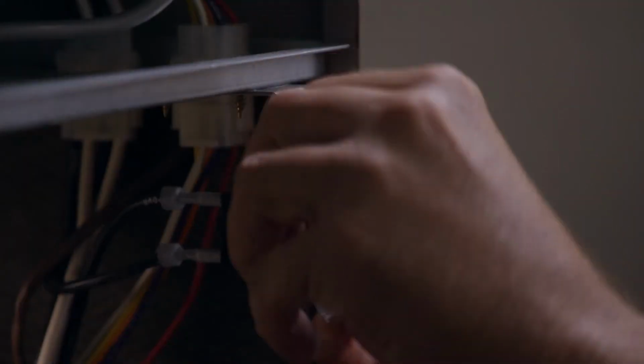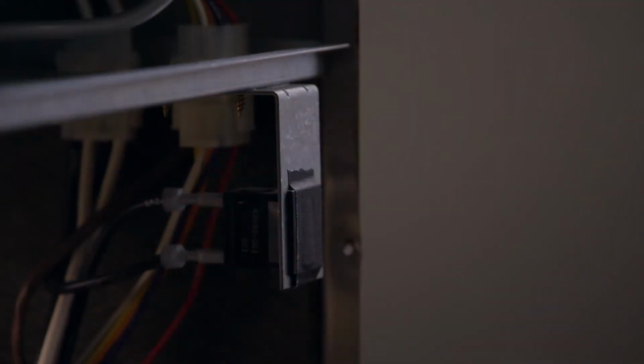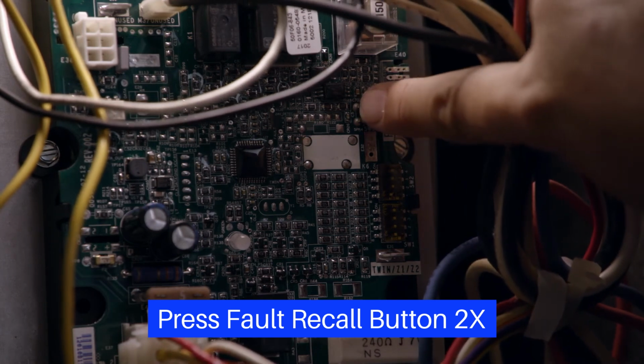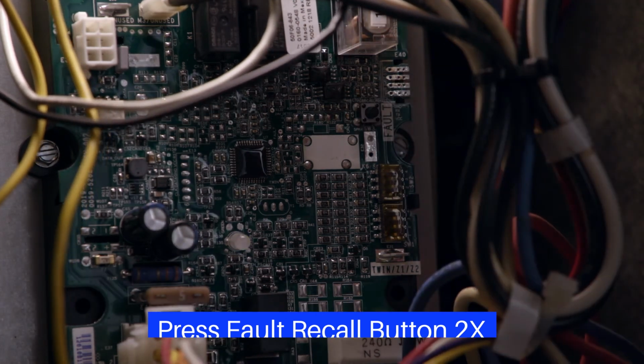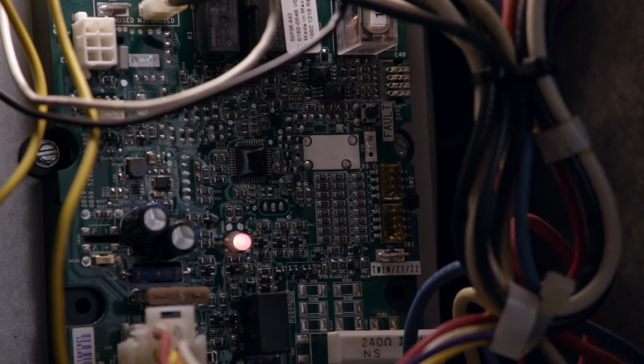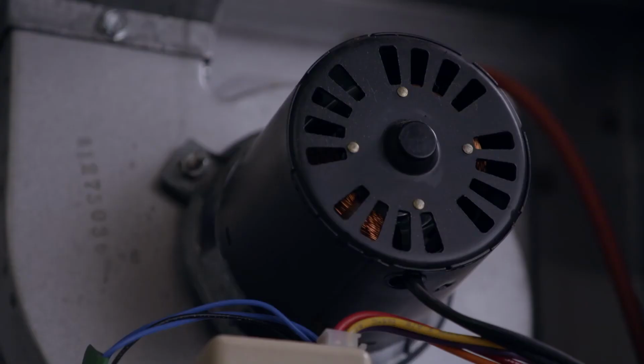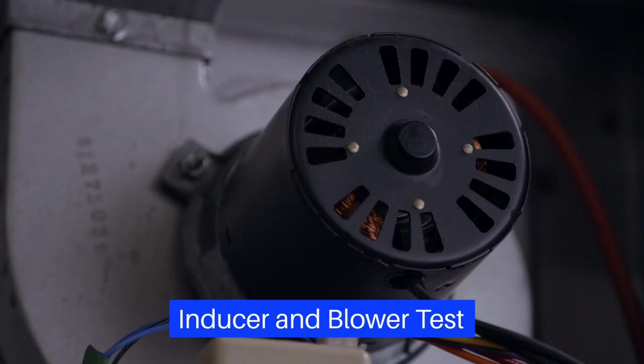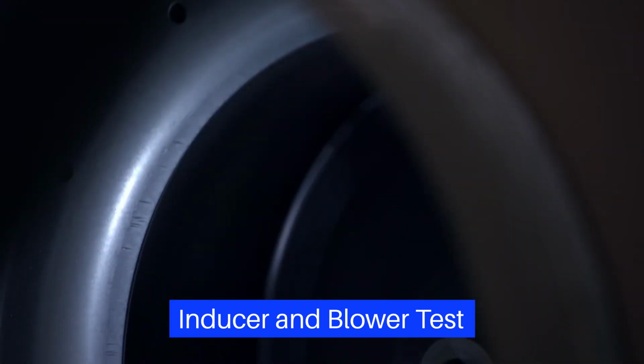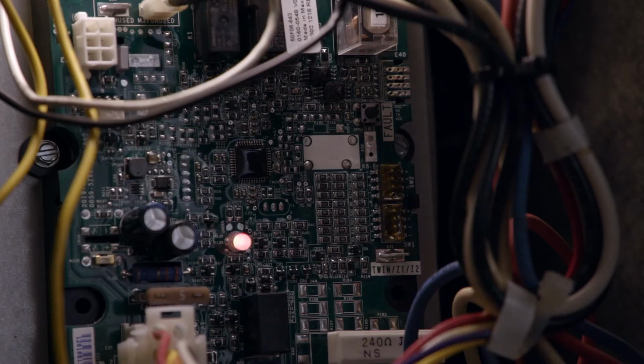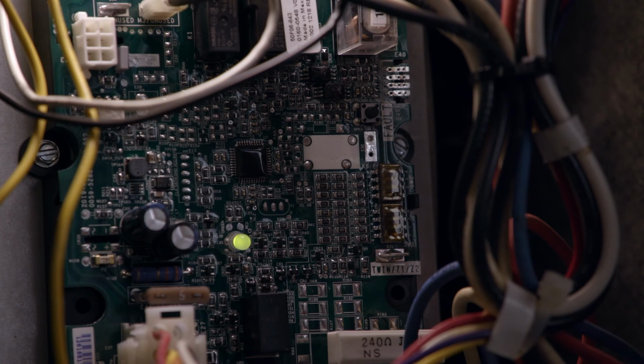To enter self-test mode, turn on power and ensure the door switch is engaged. Press the fault recall button twice within 3 seconds after powering the control. The control will enter self-test mode. If there are faults, the control's LED will first flash in red the 5 last stored fault codes. Next, the LED will slowly flash between green, amber, and red while the control runs the inducer for 7 seconds, the heat for 10 seconds, then turns them both off and runs the cool for 10 seconds before going back to standby mode. When self-test mode is complete, the control will enter standby mode and display a green LED.